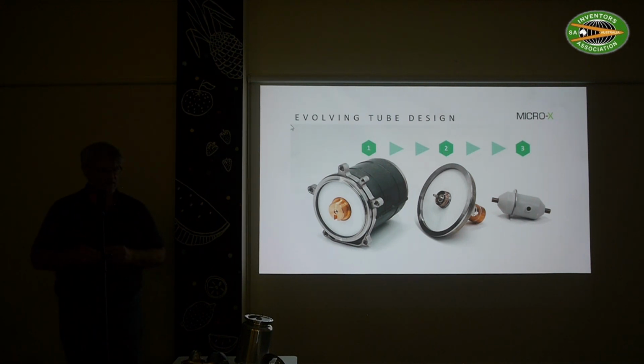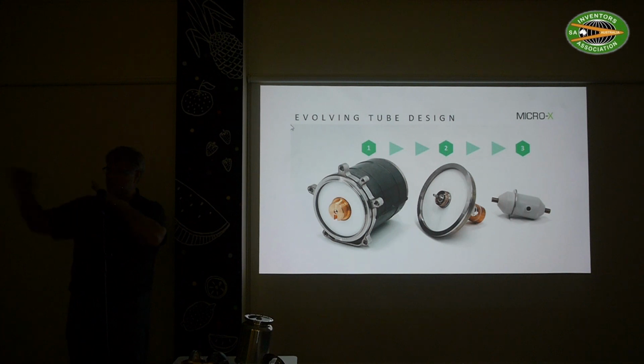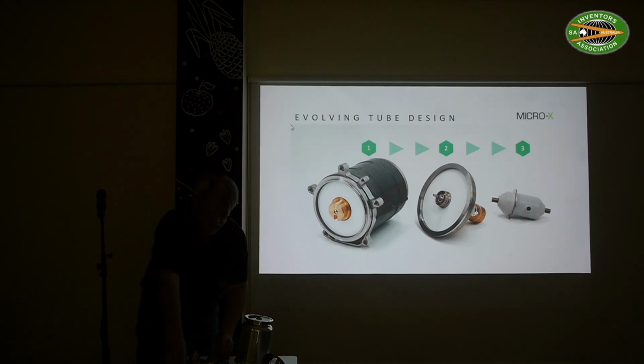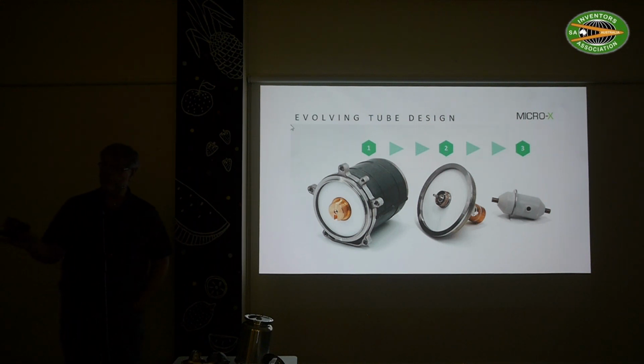That's a very good question - there are a number of aspects to it. First, the stainless steel on the outside helps with this. The anode part is angled so we bounce the X-rays in a particular direction. There's also some shielding around the tube, and this isn't lead - it's a material that looks a bit plasticky but is actually quite heavy. It's called EcoMass; it's still injection molded, but it's a plastic with really high-density fibers in it, so it starts to work almost like lead. Lead is very dense, which is why we use it for shielding, and we calculated that all this tube needs is this.